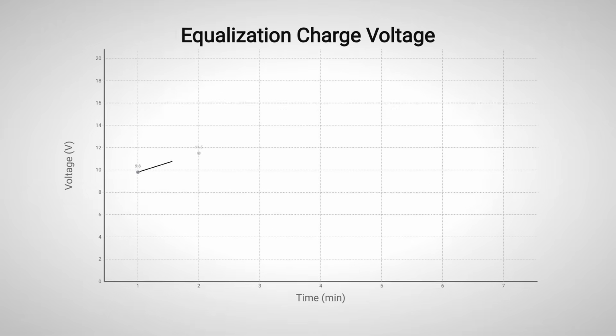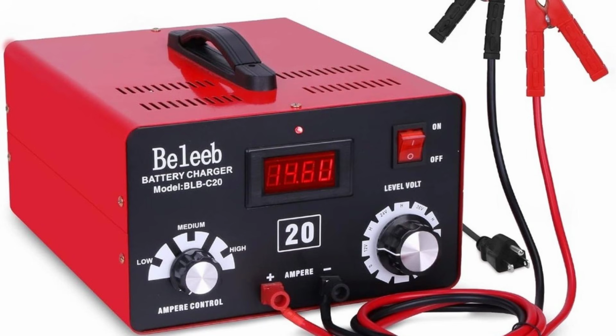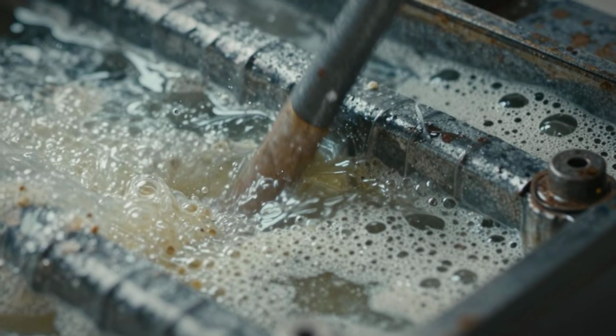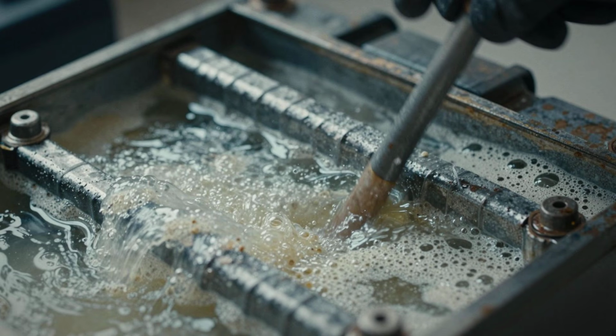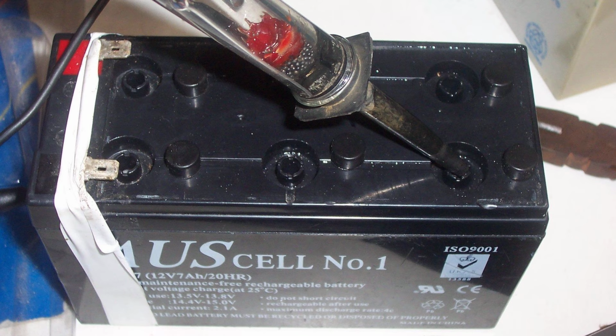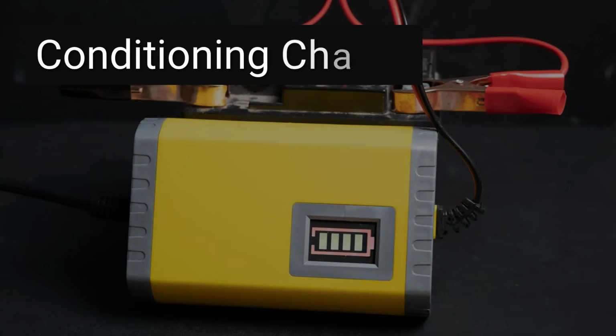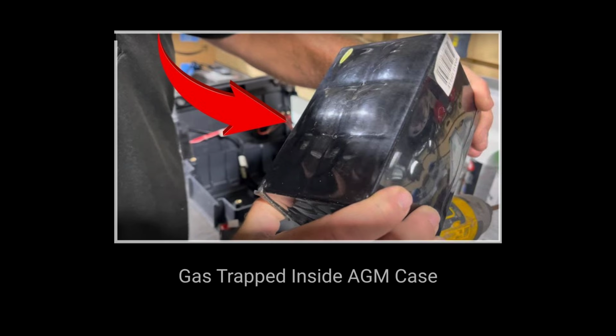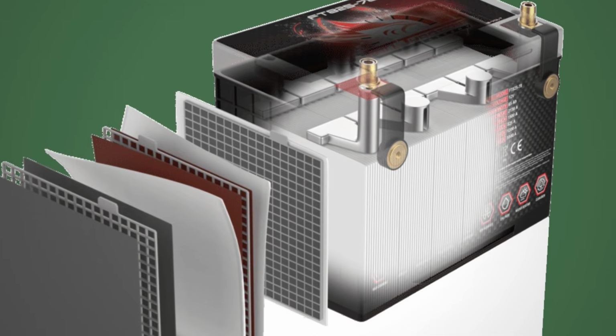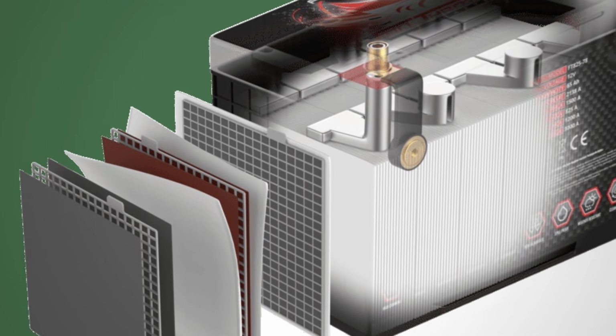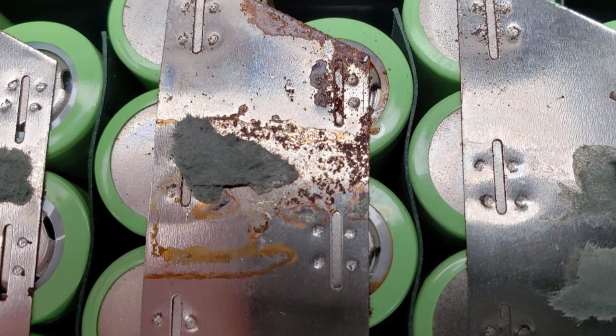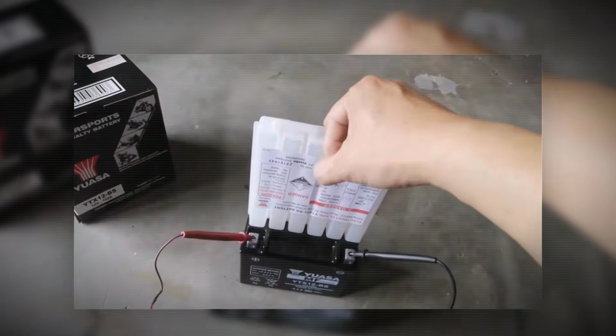You ran an equalization charge, which means raising the voltage above the normal charging level for a short period. This caused controlled gassing inside the cells, which mixed the electrolyte, broke down soft sulfation, and restored balance. Afterward, you simply topped off whatever water was lost through the caps. On a sealed AGM battery, you can technically attempt a conditioning charge. But when you raise the voltage, the gas produced has nowhere to go except through the pressure relief valve, a one-way vent designed for emergency overpressure. The hydrogen and oxygen escape into the air, and the water they came from is gone permanently. There is no cap to open.